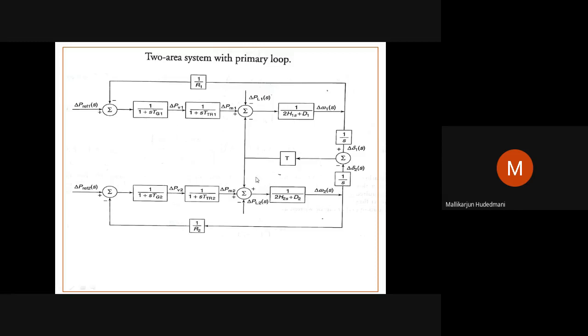Suppose there is an increase in load of area 2. Who will respond for this? Whether the generator 2 area has to respond or generator 1 has to respond. Or if there is a change in loads of area 1, is that load addressed by area 1 itself, or is area 2 also going to contribute? This is what we have to study. That is the nature of interconnected operation of the system, with only the primary loop.